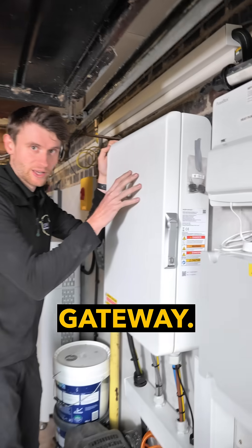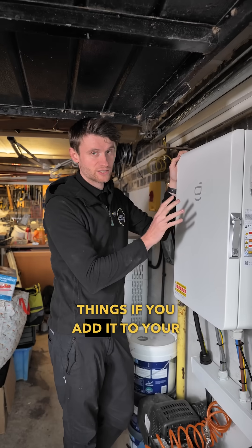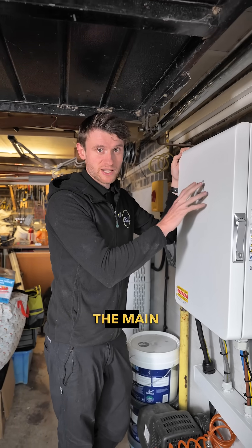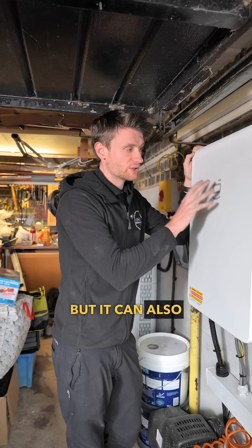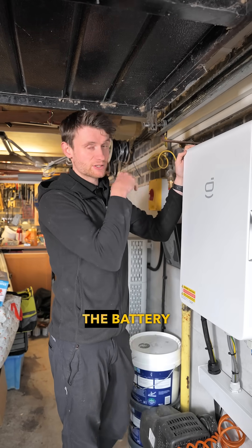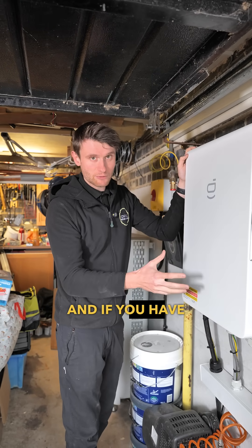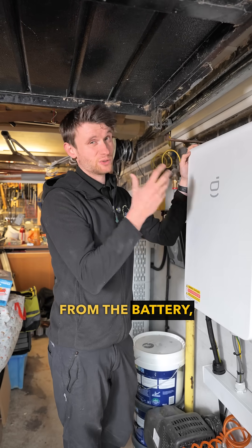Firstly we have the backup gateway. This isn't absolutely essential but it does some really cool things if you add it to your install. This monitors the main supply so it can tell the system if you're importing or exporting, but it can also take the battery off grid. That means it takes the battery into islanding mode, and if you have a power cut it will resupply the whole house from the battery, which is pretty cool.